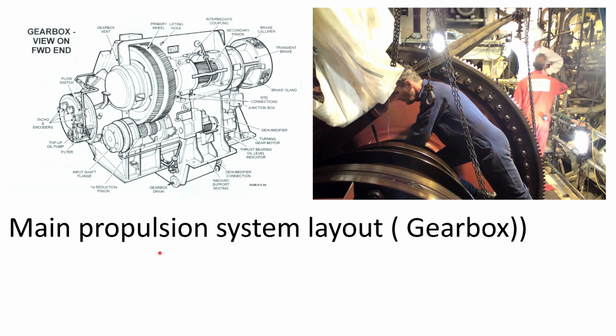Because the gearbox must not turn unless the gas turbine is on and selected, the clutch mechanism on the gearbox is more complicated than it would be on a Type 42. In addition to being more complicated because it needs to be controlled in and out, rather than a simple ratchet-type design where you spin up the engine and it locks itself in, the clutch is also on the output side of the gearbox, which is the high torque side.